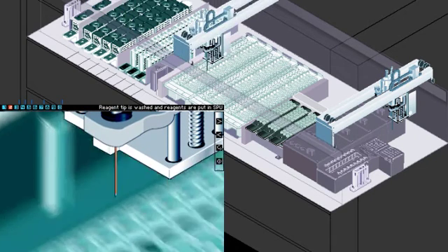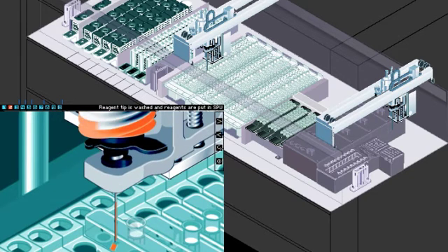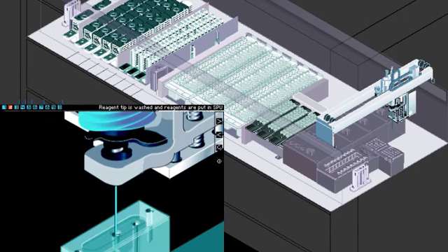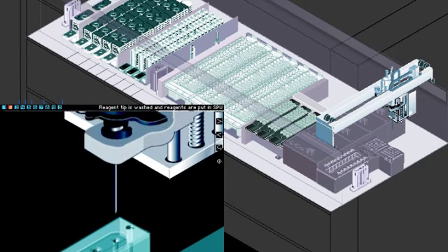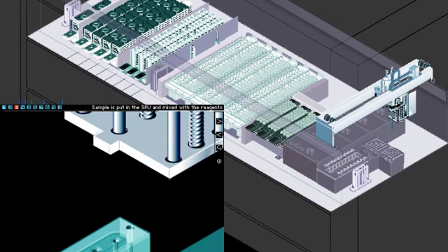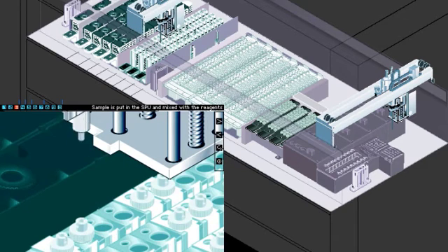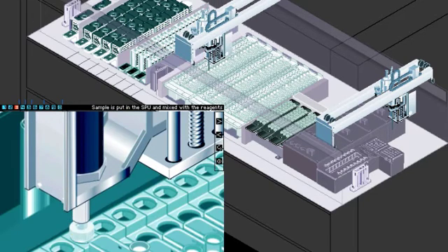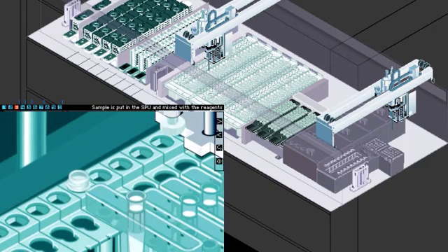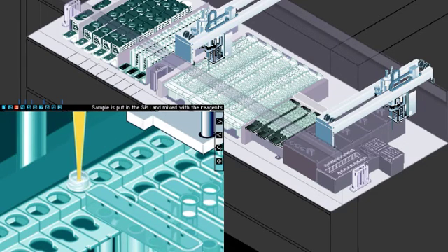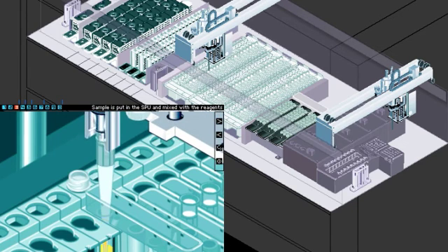The Ampliprep system pipettes in the QS, lysis, and probe reagents. The system moves the patient specimen tube into the sample processing unit rack, automatically opens the lid of the tube, and pipettes the specimen into the 60-degree processing chamber using a dedicated single-use pipette tip. There, the reagents and the specimen are mixed, and the specimen tube automatically closes.